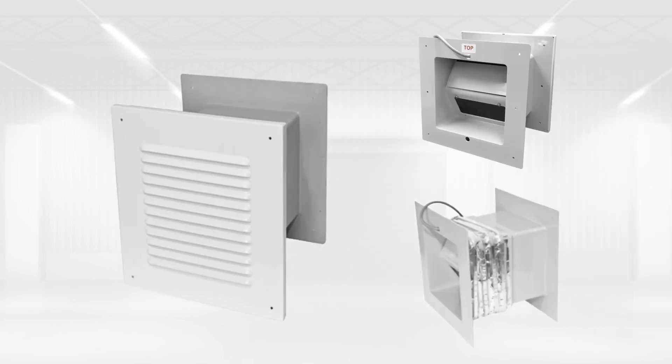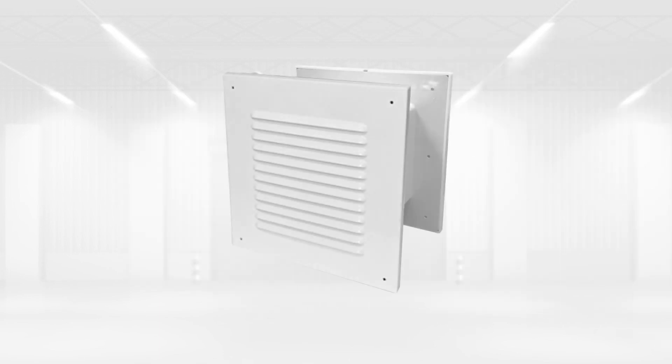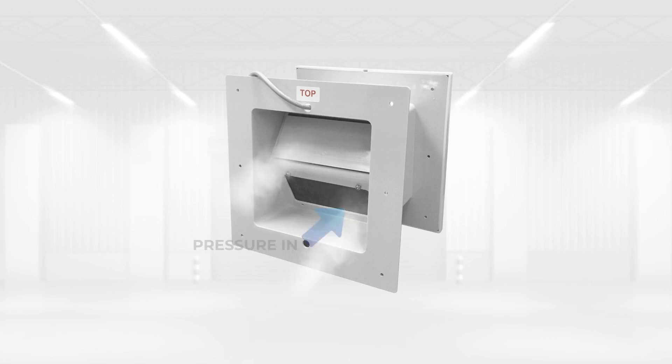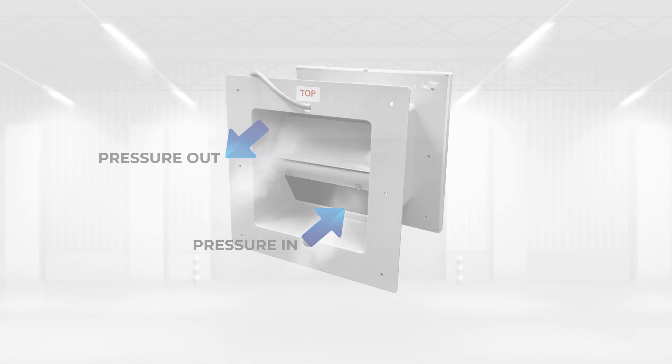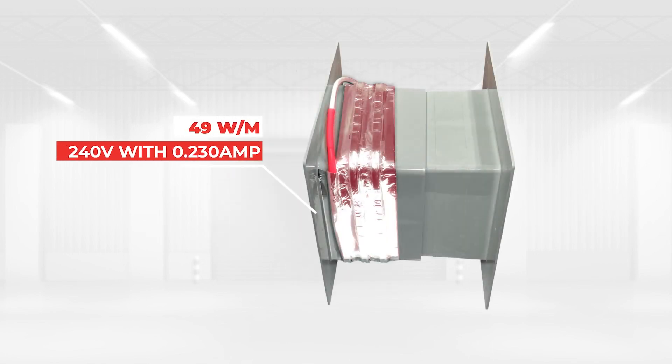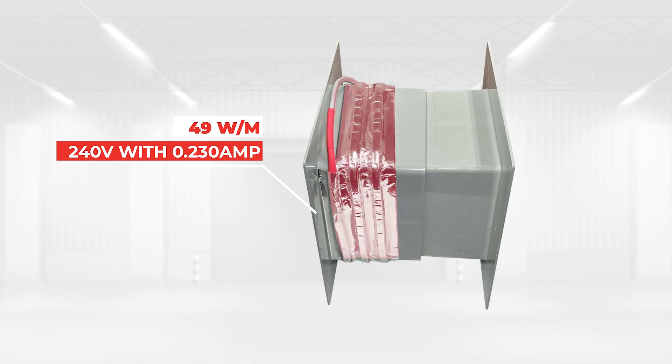CRH-1000 series pressure relief valve. The CRH-1150 is a heated mechanically operated valve with two sealing flaps allowing airflow in either direction. The heating element is a 49 watts per meter self-regulating heater cable, 240 volts with 0.230 ampere draw.